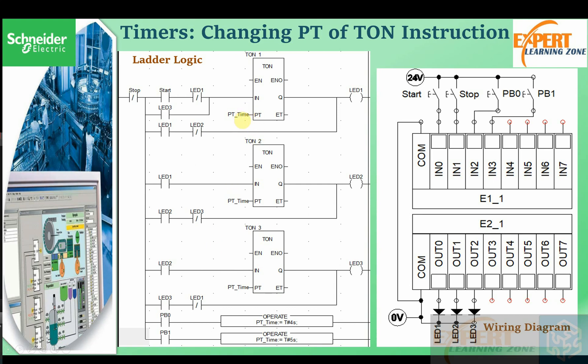What has happened is that we have now defined a variable called PT, and this variable is the one we are going to be changing dynamically. We have added one new block: when push button zero becomes pushed, this contact closes, the block operates, and it assigns the time of four seconds to the PT so all timers become four seconds.